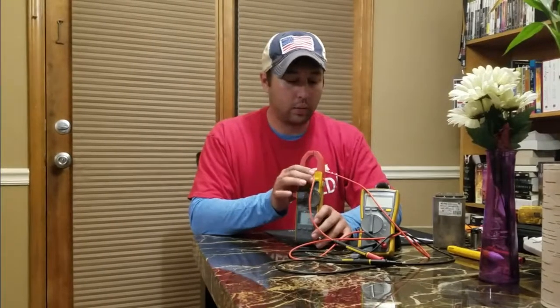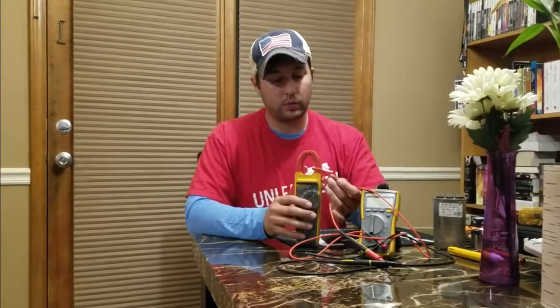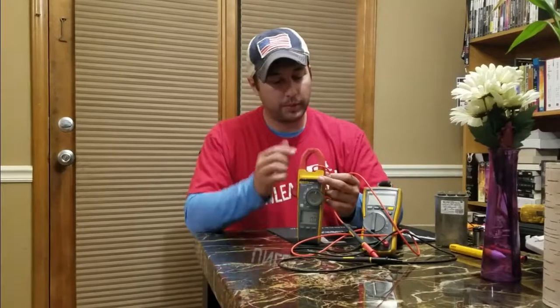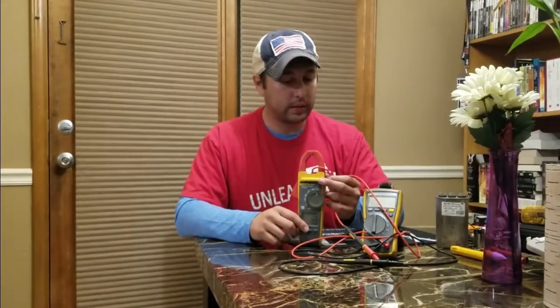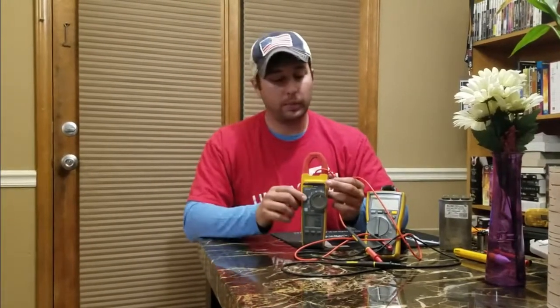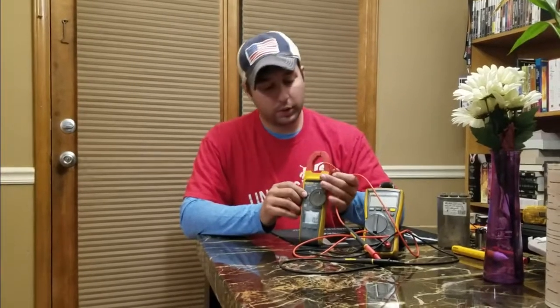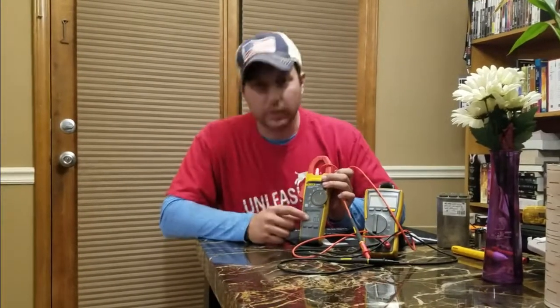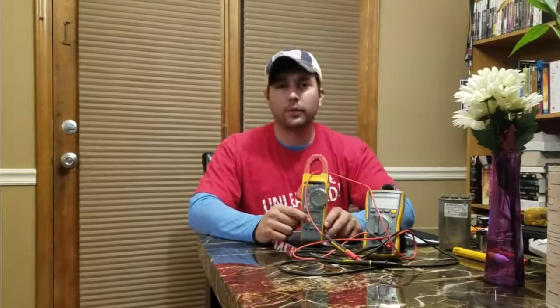The reason you're going to want this amp measurement is because you can wrap it around a wire, and we're going to pretend that we have power moving through here. Let's say it's a condenser fan motor. It's going to be pulling about 1 amp. So we check that, and we go down here to our screen, and we see, oh, it's pulling 3 amps.